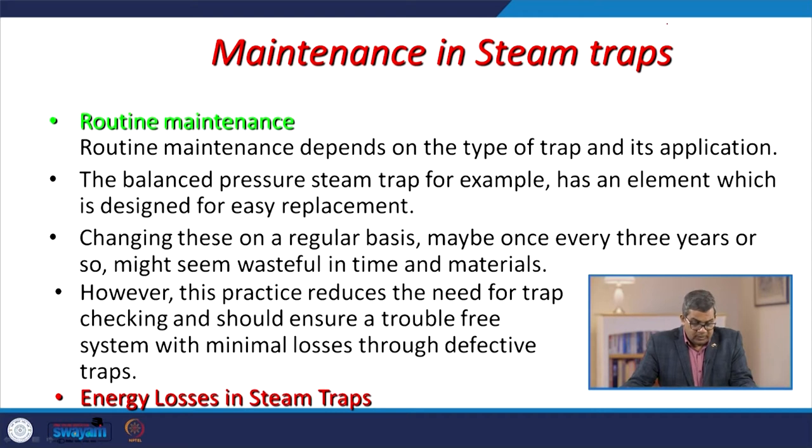So, there are a couple of aspects attributed to the maintenance in a steam trap. One is the routine maintenance. Now, the routine maintenance depends on the type of the trap and its application. Like a balanced pressure steam trap, for example, has an element which is designed for easy replacement. Changing these on a regular basis, maybe once every 3 years or so, might seem wasteful in time and material.